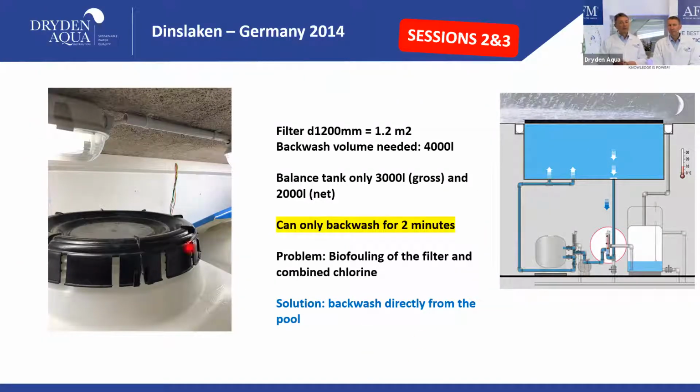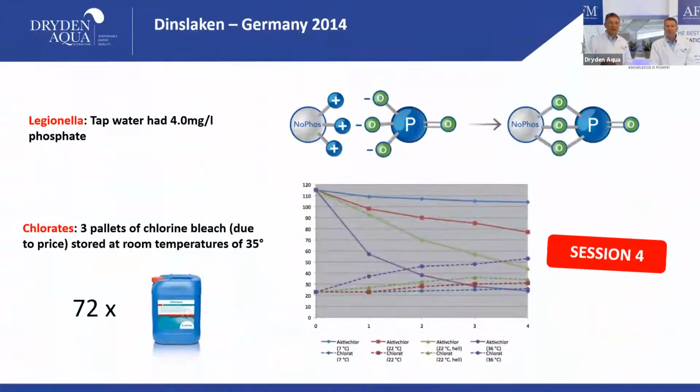By the way, Philip, what's the problem here? Well, this was not in this installation. This is you cannot access the balance tank. So if you cannot access it, you cannot get in, clean it. This is from one of my Swiss customers. How do you want to get in and to clean this? How do you want to do this? I mean, it's 20 centimeters. I mean, too small for me and for you. Impossible. So these bad things you should not do. This is not good. Yeah.